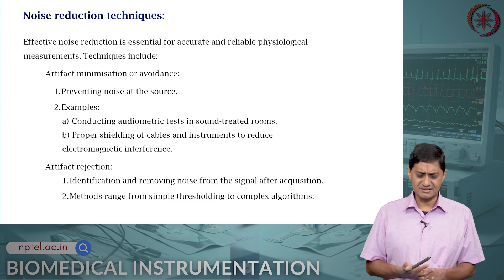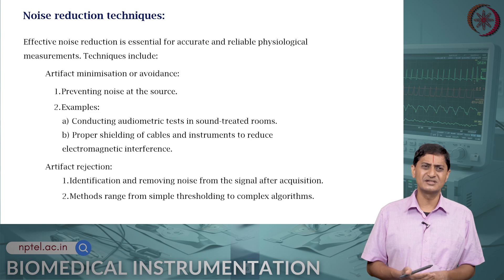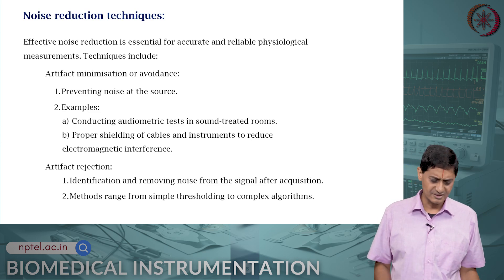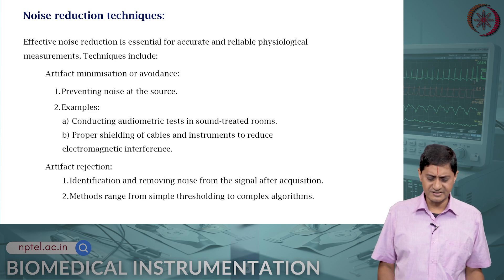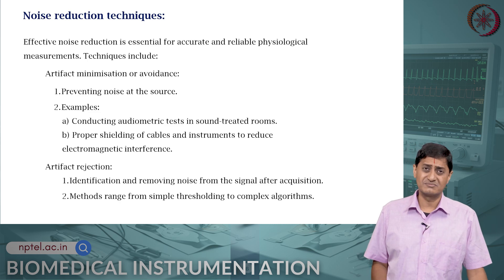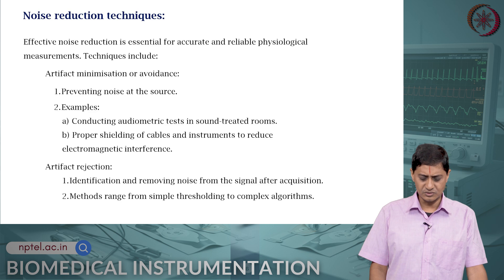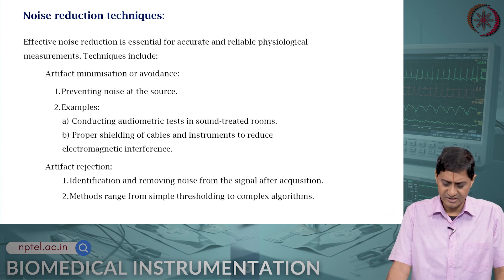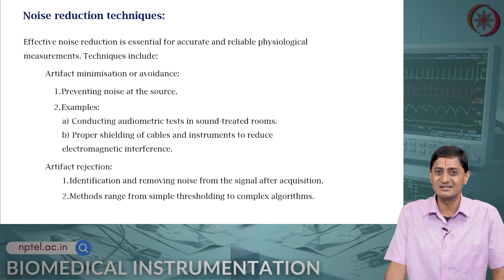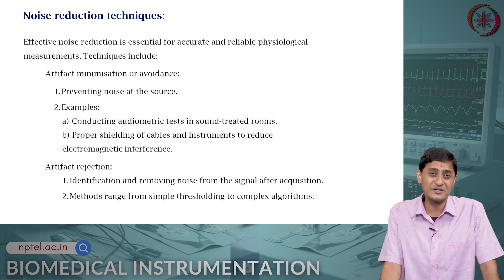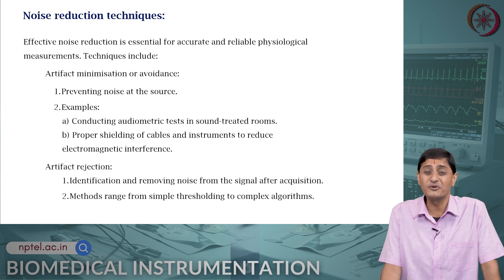Effective noise reduction is essential for accurate and reliable physiological measurements. Techniques used include artifact minimization or avoidance — the first step is to minimize noise at the source. For example, if you are measuring audiometric signals, sound-proof the room so there is no external noise. Proper shielding of cables can help reduce electromagnetic interference. Identify and remove sources of artifacts. For example, eye blink is a common artifact in EEG — you can request the participant not to blink, though it is not always possible. If they do blink, advanced signal processing techniques are needed to remove the eye-blink artifact.